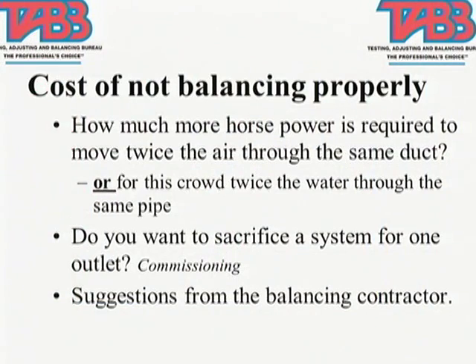And when you start looking at it like that and you say, I'm going to start using 8 times the energy and the commissioning agent's making me do it because they don't understand the system, what kind of trouble does that lead to for the customer or the end user? Its energy costs are higher. Do you want to sacrifice a whole system for one outlet? The commissioning agent, if it's a checklist commissioner, they do.